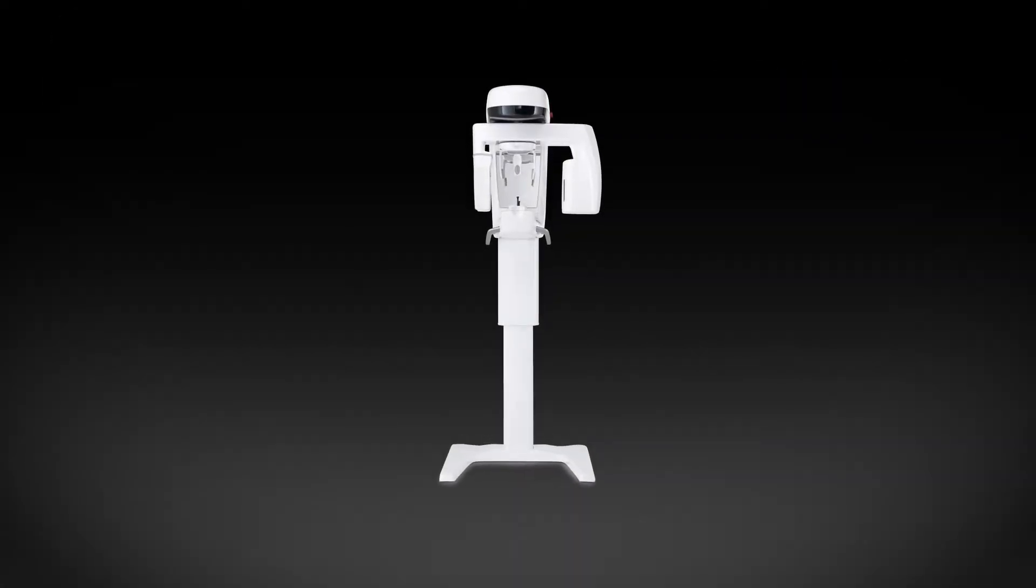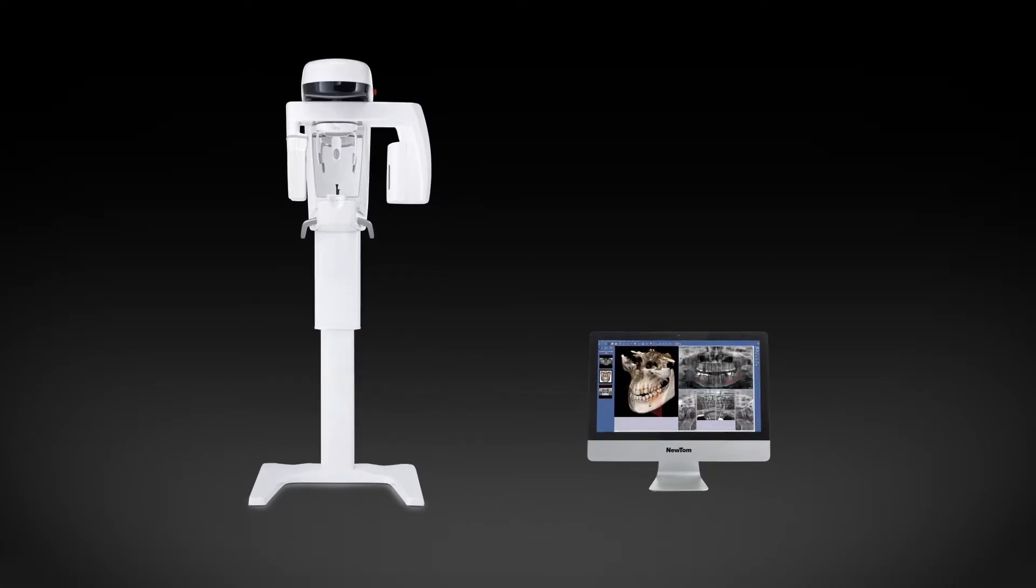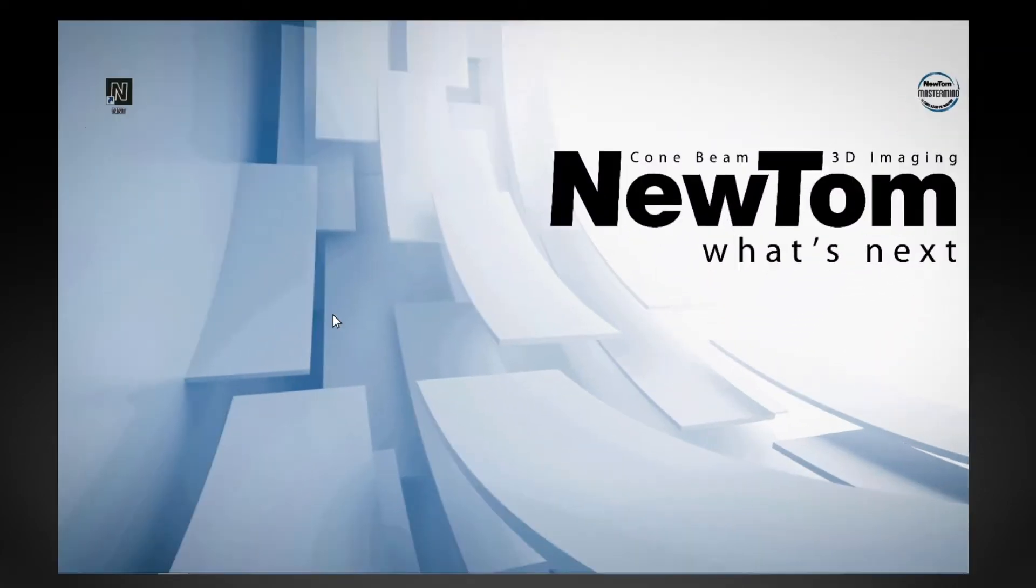3D scanning is only possible if Newtom Go is connected to a PC with the NNT software installed. First, launch NNT by clicking on the desktop icon.